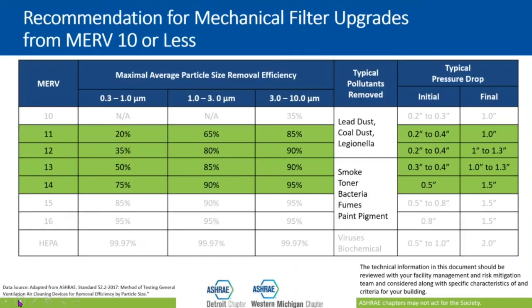So instead of selecting HEPA filters that are going to have a significant pressure drop, much higher than the filters that were likely already in the system, what we're suggesting here is that folks look at levels between 11 and 14. And we go down to 11 because a lot of facilities have older buildings, equipment that was designed, particularly in schools. We see a lot of unit ventilators, and these systems had filters that didn't even have MERV ratings, or if you did an equivalent MERV rating for what they are today, it would probably be MERV 3 or MERV 4, right? It wouldn't even be the typical MERV 8 that you see now. And so we're suggesting that folks go with something, again, between 11 and 14.